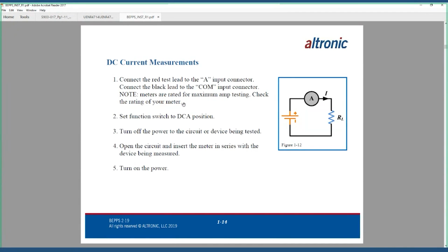And like that example I showed a few moments ago, that particular meter had an amperage port for larger flow rates, as well as a milliamperage port for smaller flow rates. Set the function switch to DC amp position, turn off the power to the circuit or device being tested, open the circuit and insert the meter in series with the device being measured. So what we do is we actually break the circuit and we connect our red test probe to the battery supply and run it through our meter, and then out the black test probe from our meter back into the circuit to complete the circuit. So we're actually completing the circuit with our meter inserted in there so we can get an amperage reading.